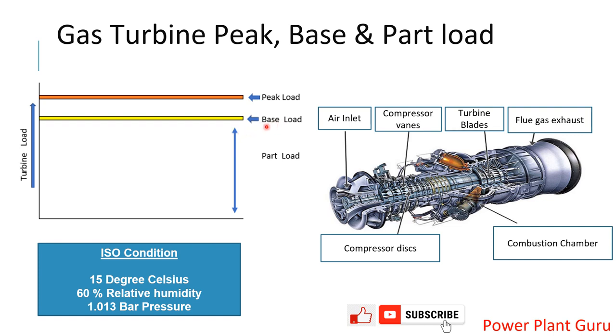At base load, where IGV is fully open, you will see on your gas turbine HMI that the machine status shows 'base load.' When you select peak load condition, the machine output increases — at least 8 to 9 percent of base load capacity — and the machine reaches peak load condition. At peak load, exhaust temperature is higher and airflow is limited, so only additional fuel is given, placing higher thermal stress on the machine. Return to base load as soon as possible. In this video we discussed base load, peak load, part load, and ISO conditions.